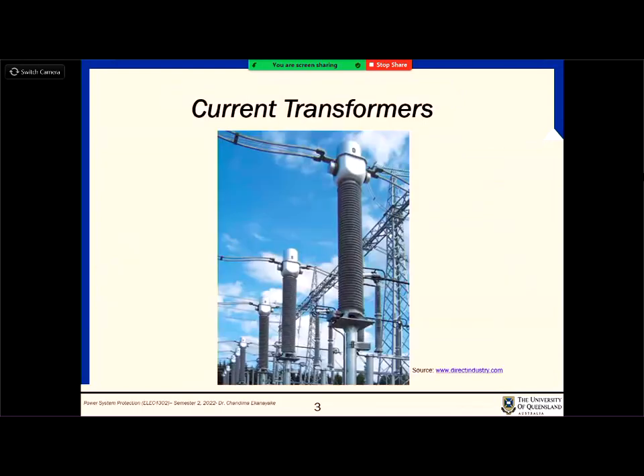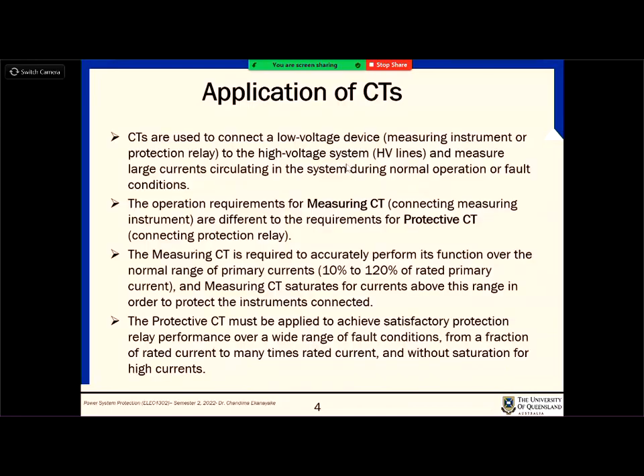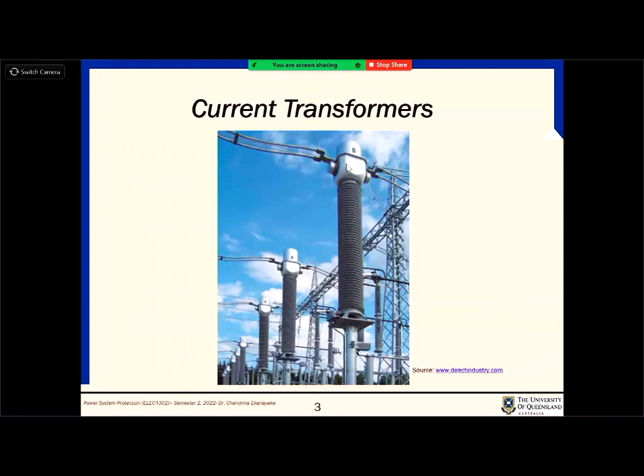So this is a typical current transformer. I think I showed this picture previously when we started the course. You can see that they have two live connections: one is the current coming in and the other is the current going out. Inside this you have the measuring arrangement. There will be a couple of slides about the internal construction. This side of the column is grounded. In a CT, inside this, basically this is the wire, and then some sort of toroid is like that. So this is the connection that you have inside, right?